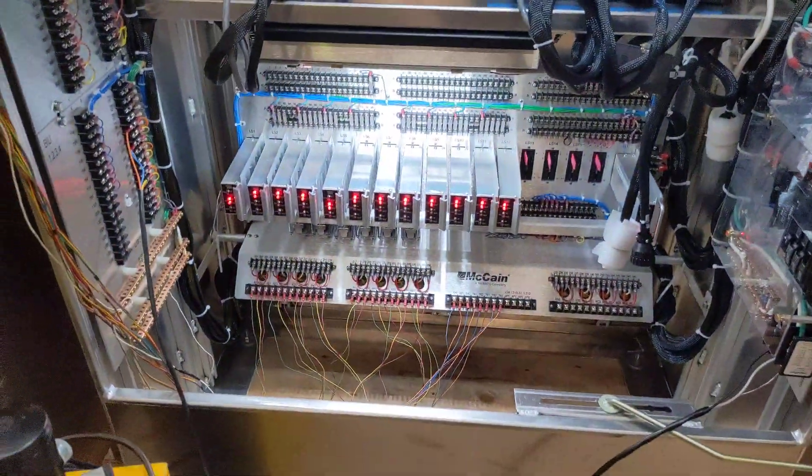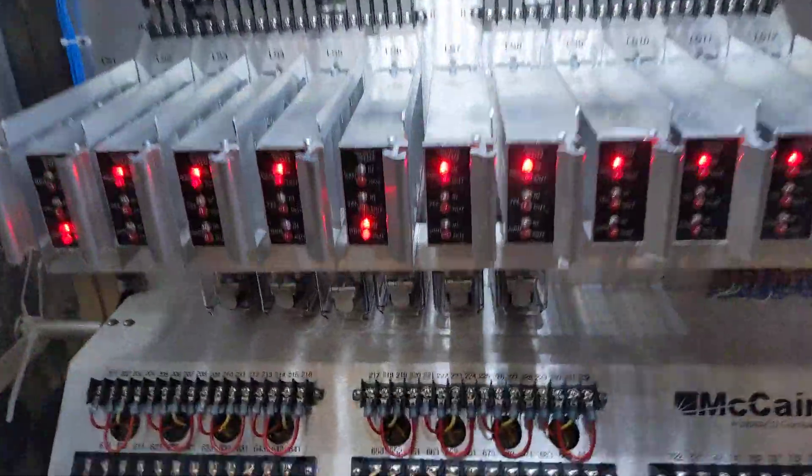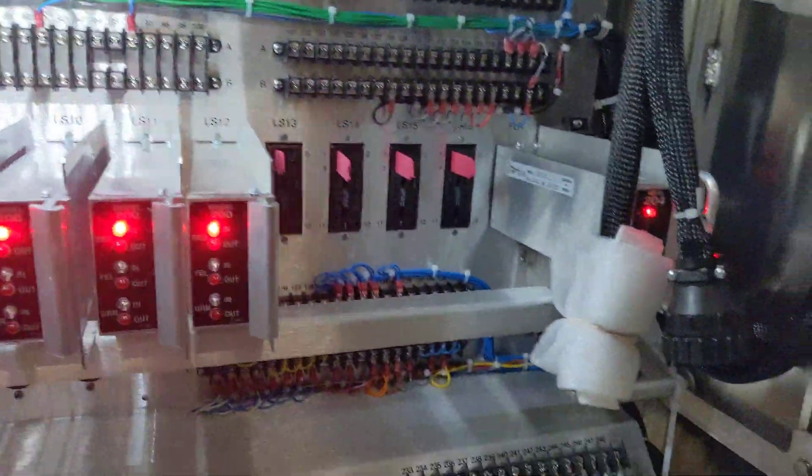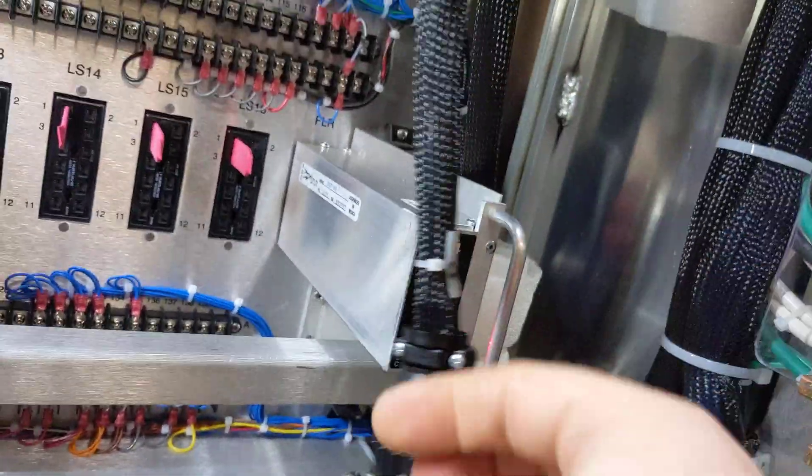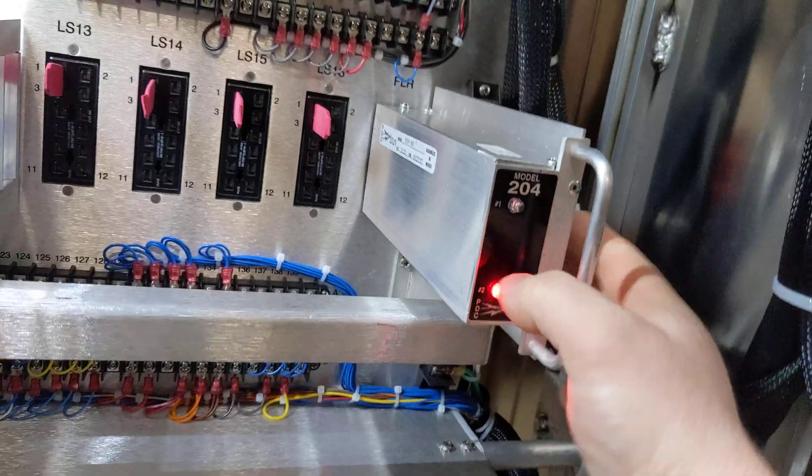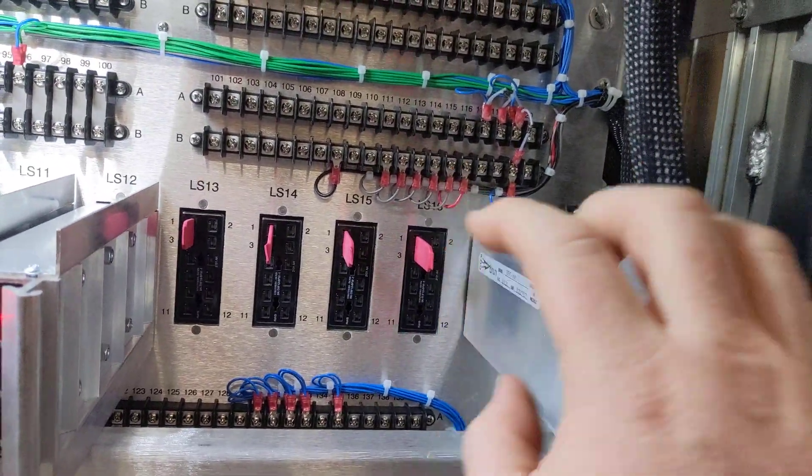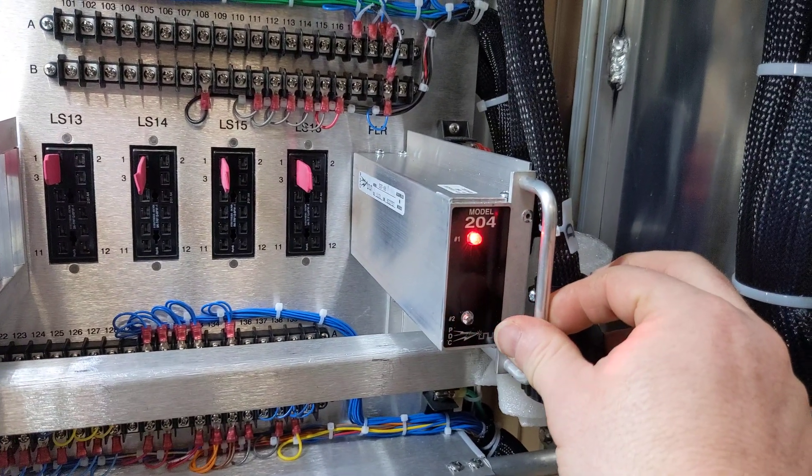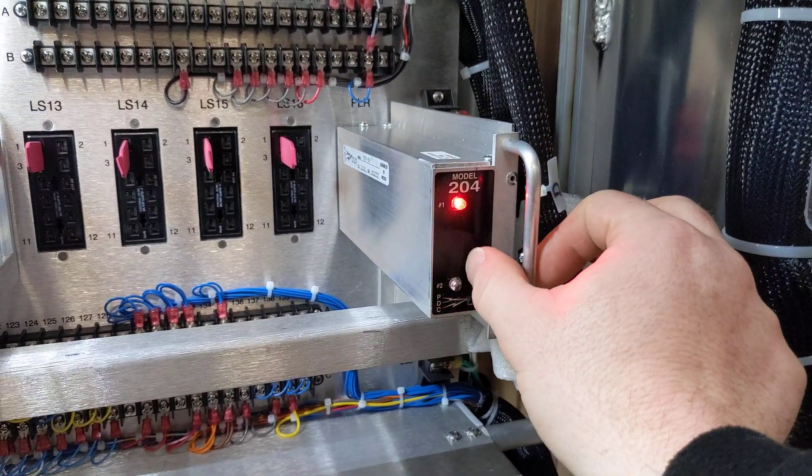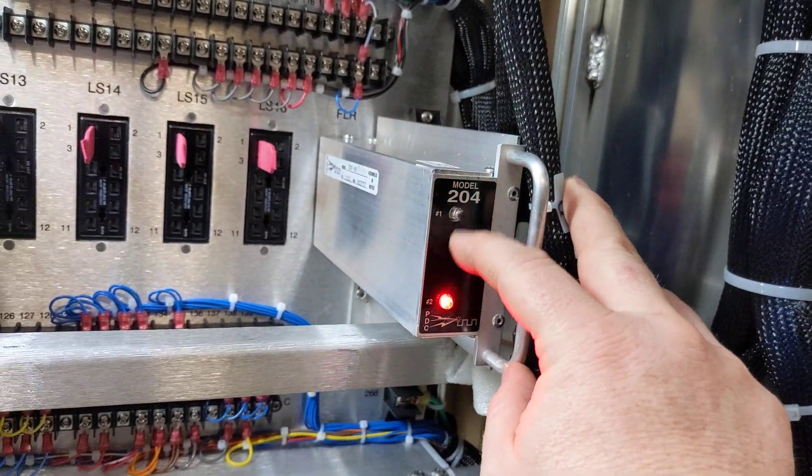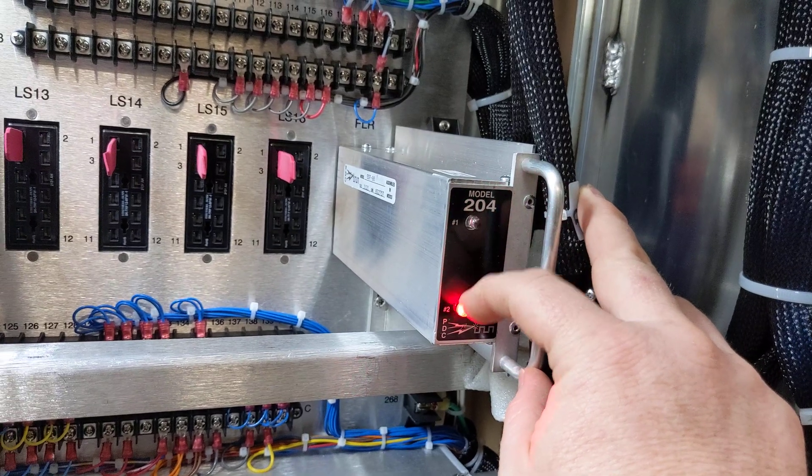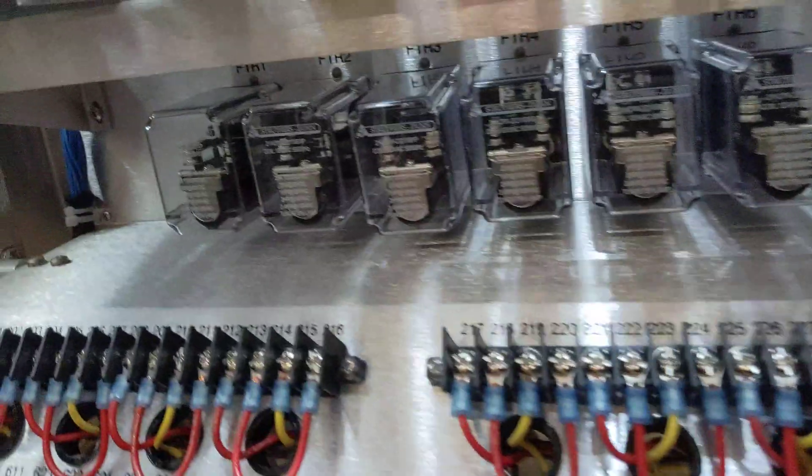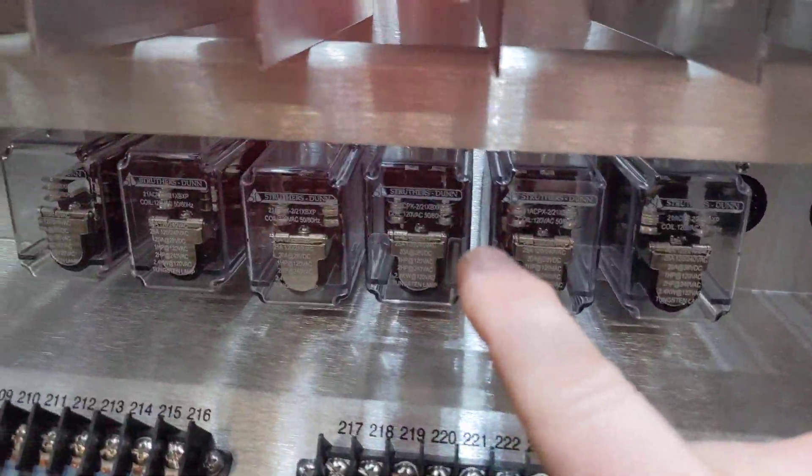So that being said, down below here, we have a flasher assembly. Right here we have a NEMA flasher. And this circuit is being driven from outputs that are on the back panel, they're wired in back here, driving this guy constantly. So you basically have a similar output, like a load switch, except this is 120 volts switching back and forth, all day long, 24 hours a day, 7 days a week, just sitting there waiting for these guys to switch.